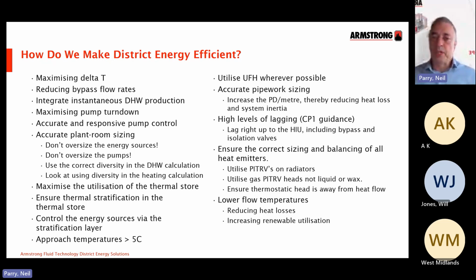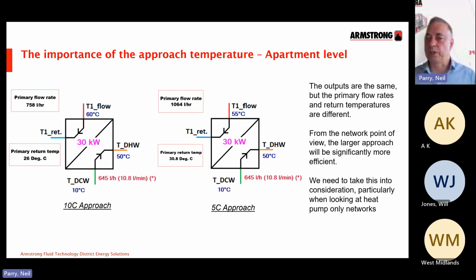So just looking at approach temperatures, I've done a couple of calculations here, looking at terminal units that you would typically get in an apartment. These would be HIUs here, and we've got a 10-degree approach on the left-hand side and a 5-degree approach on the right. Same demands, 30 kilowatts here, and what you can see is at a 10-degree approach, you have a primary flow rate of 750 litres per hour. With a 5-degree approach, that increases from 758 to 1064, but it also is damaging to the return temperature. The 10-degree approach will give you a 26-degree return, whereas the 5-degree approach gives you a 30.8-degree return.